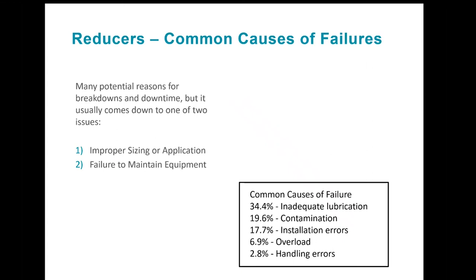What can cause a failure in a gear reducer? Mechanical failures are a concern with any application because when systems go down, it results in lost productivity and by extension money. Like all rotating equipment, there are many potential reasons for breakdowns and downtime, but it usually comes down to improper sizing of the application or failure to maintain the equipment. As shown here, 34.4% of common failures are due to inadequate lubrication, 19.6% contamination, 17.7% installation errors, 6.9% overload, and 2.8% handling errors. Oil analysis falls under the umbrella of equipment maintenance.